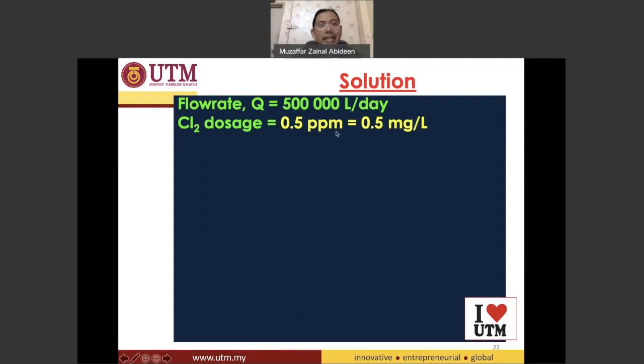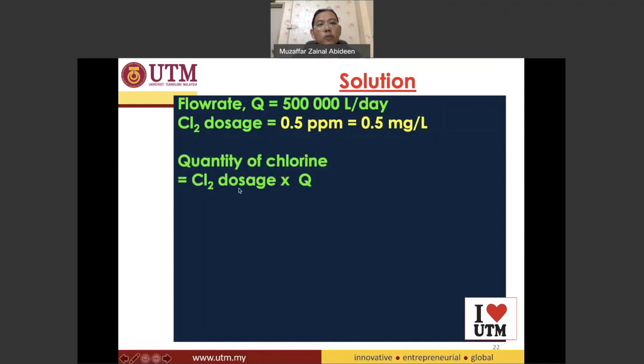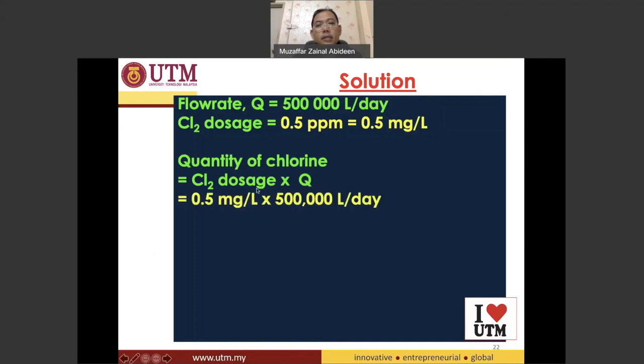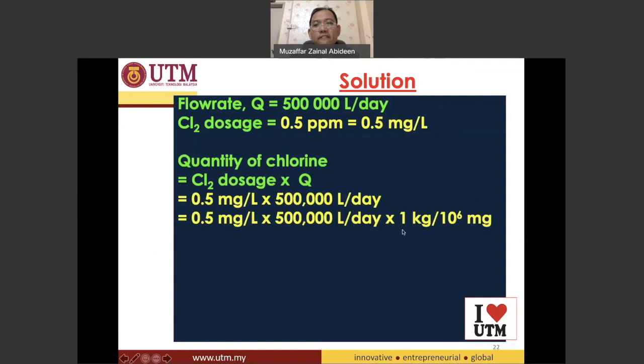PPM, or parts per million, equals 0.5 milligrams per liter. To find the amount of chlorine needed, we multiply the dosage by the flow rate: 0.5 mg/L × 500,000 L/day. The liters cancel, giving milligrams per day. Since milligrams is too small, we apply a conversion factor to kilograms, so milligrams cancel and liters cancel, giving the answer in kilograms per day.